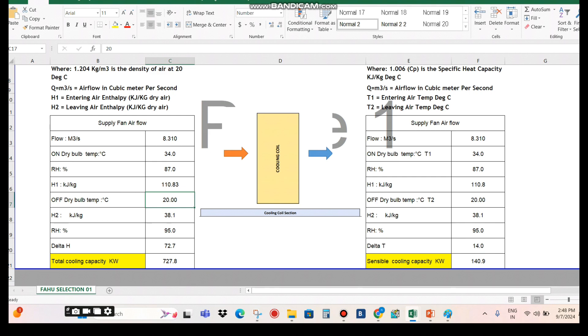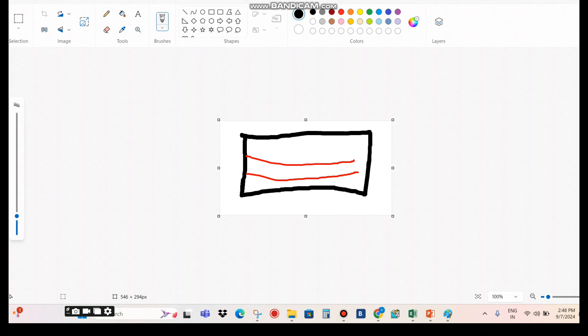Additionally, it's important to note that the FAHU is not the only cooling source — it provides fresh air only. Each room also has an FCU (fan coil unit) which provides the comfort condition of 23°C. The FAHU is specifically for fresh air to meet indoor air quality requirements. Accounting for 2 to 3°C heat gain and leakage losses, I consider 20°C as the off-coil dry bulb temperature for the FAHU.